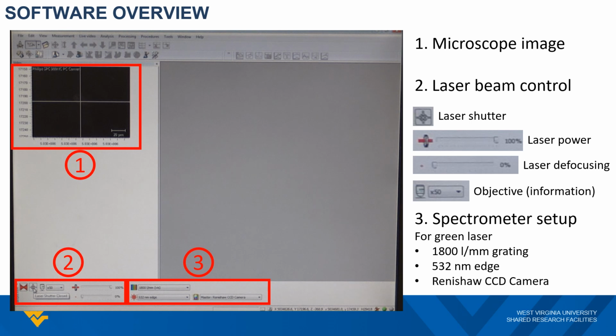including open and close laser shutter button, and a sliding bar that will allow you to adjust the laser power on your sample. Also another sliding bar that will allow you to defocus the laser on your sample if needed. There's another objective button that will allow you to input the objective information, which will create a correct scale bar on the image window. Notice that you will need to change the objective manually, while this button is mainly for the information.